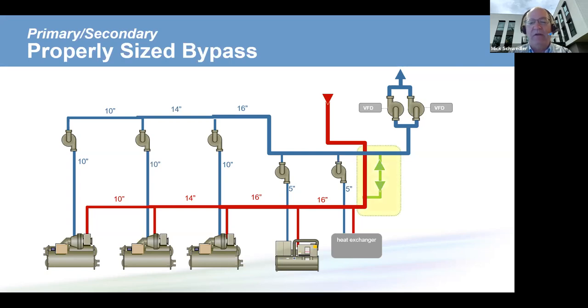We look for the bypass line. The bypass line is going to be a pipe between the chilled water supply and the chilled water return. And generally, it's going to be between the secondary pumps, the distribution pumps, and the chilled water pumps. In this case, we see that the bypass line is a 10-inch bypass, and therefore it's really a quick way to find out, is the bypass line the right size?